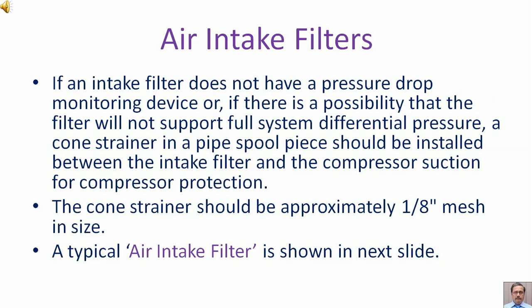If an intake filter does not have a pressure drop monitoring device, or if there is a possibility that the filter will not support full system differential pressure, a cone strainer in a pipe spool piece should be installed between the intake filter and the compressor suction for compressor protection. The cone strainer should be approximately 1 by 8 inch mesh in size.